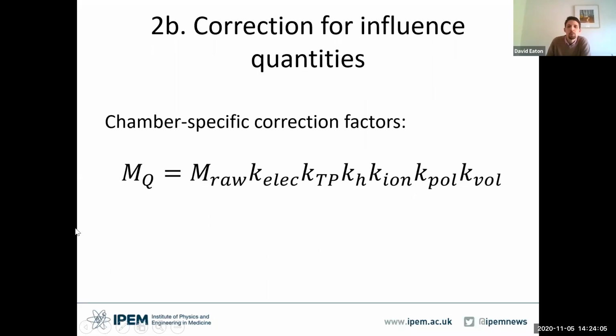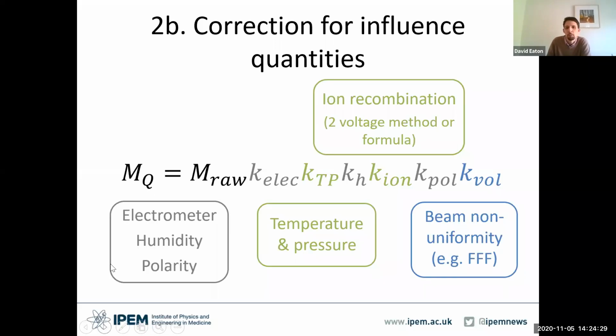Now, as many of you will know, we need to correct our raw chamber reading for some influence quantities. And this approach essentially hasn't changed since the previous iteration of the code. We've added a little bit more detail on some aspects and a bit more clarification. And these are all the different things that you might need to correct for, all these different k factors for different aspects of the environmental conditions or the setup. But as you'll probably know, there are two that we need to be particularly careful of, and that's the temperature and pressure, and the ion recombination, particularly for flattening filter-free beams. The ion recombination values can be quite large. We can be talking well over 1%.